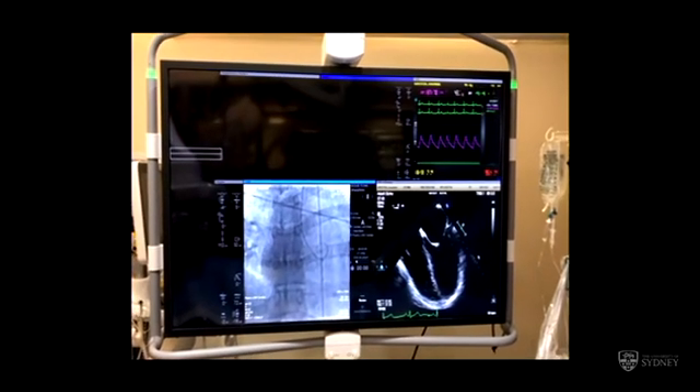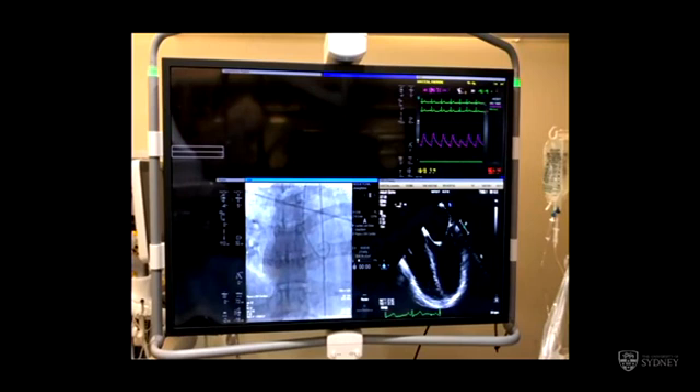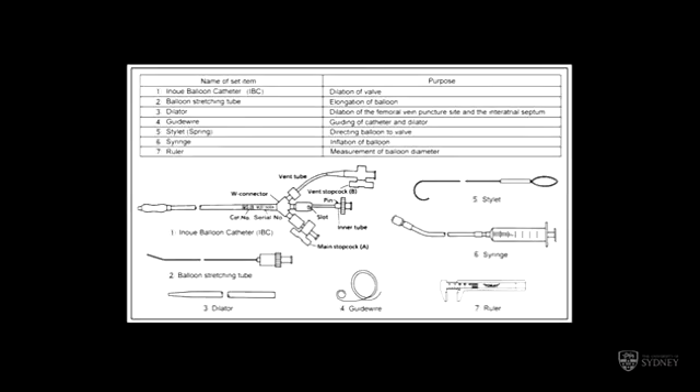This shows the lab setup: fluoroscopy on the bottom left, transoesophageal echo on the bottom right, and haemodynamics on the top right. This balloon is I think the most clever piece of apparatus we use in interventional cardiology — and I regret to inform you it was actually designed by a surgeon. The balloon itself has an inner tube, de-airing vents, and an inflation vent. It has a balloon stretching tube that you can use to stretch the balloon out — making it about twice as long and correspondingly half as wide, which is very useful for not leaving a big hole in the femoral vein or the atrial septum. It comes with a clever guide wire that has a very stiff shaft but a soft pigtail at the end, plus a stylet that acts as a steering device for the balloon into the mitral valve, a syringe for inflation, and so forth.